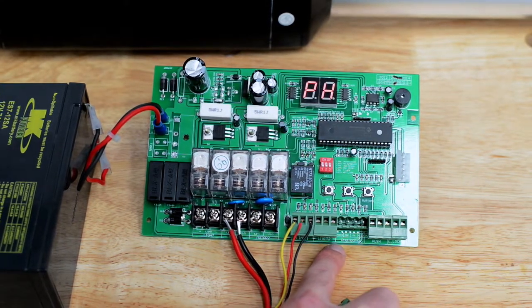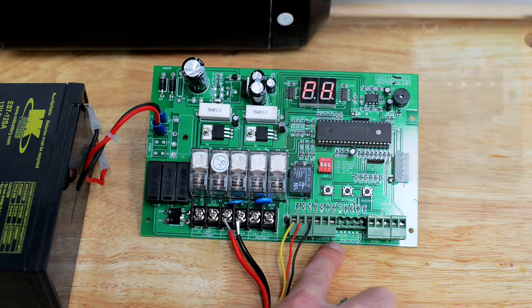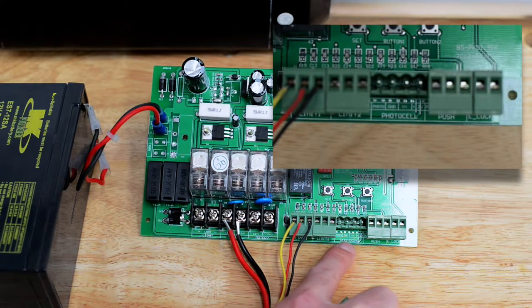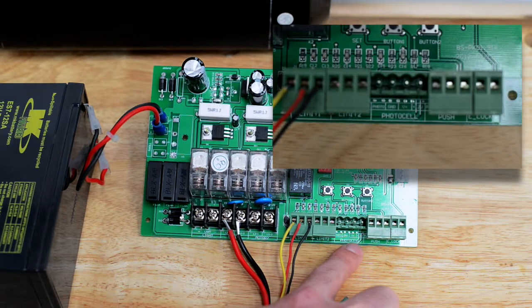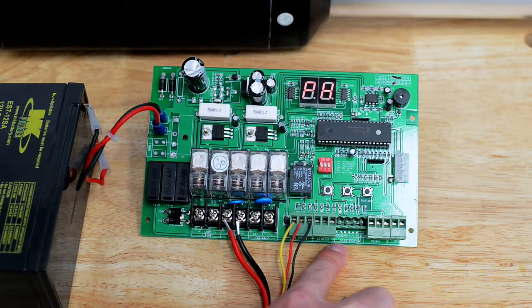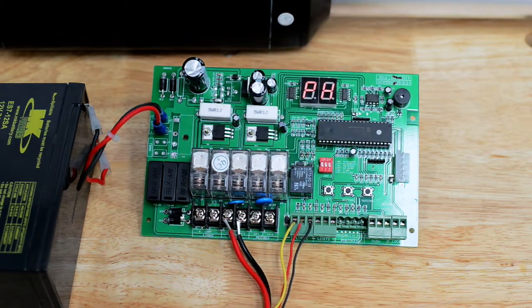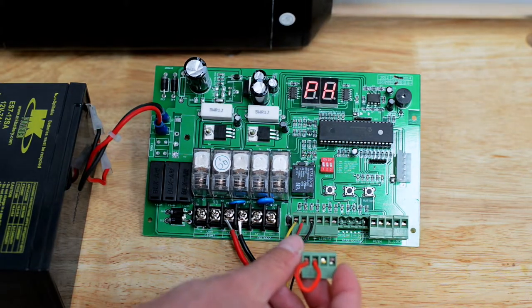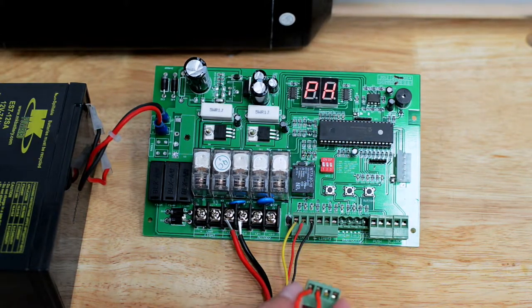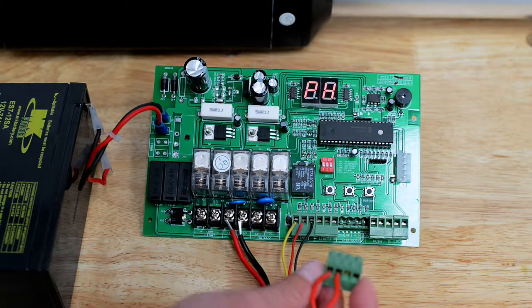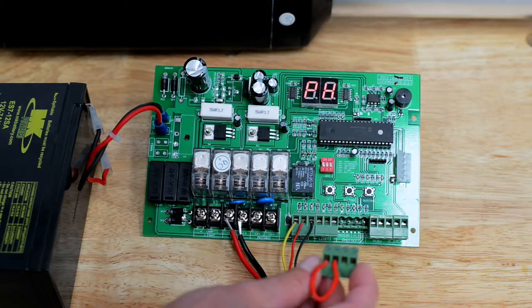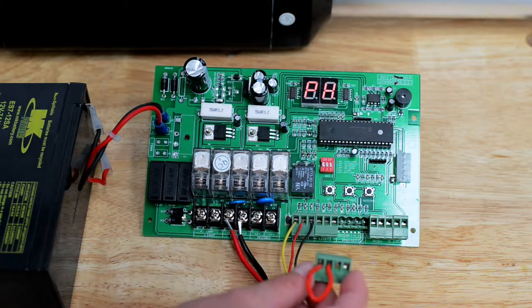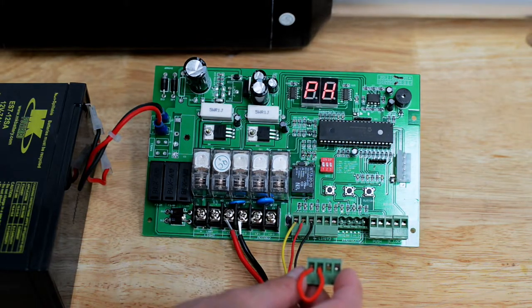On the photocell terminal we have the terminal photo ground, V positive and positive 12 volt. Photo and ground are very important. These are the two terminals that we have the jumper in. If you are not using a safety device, which we do always recommend to be used, you need to install a safety jumper where the safety device would be.